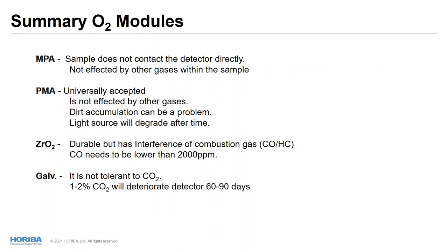So, a summary of the O2 modules. MPA is one of the recommended best ways to measure O2 because it has no direct contact with the sample and is not affected by other gases either. PMA is universally accepted with no major effects. Its durability may be lower than MPA, but it is still pretty durable and robust. The zirconium method has some disadvantages: it suffers interference from combustion gases such as a high concentration of CO, or hydrocarbons. Please make sure your sample doesn't have more than 2000 ppm of CO.